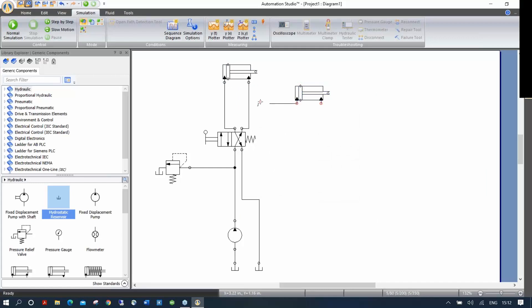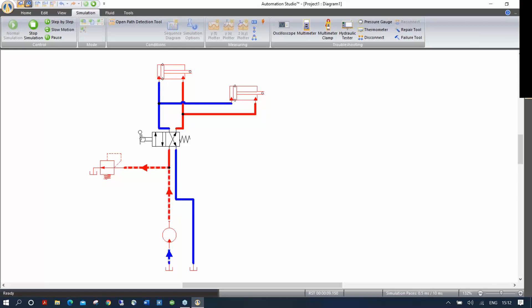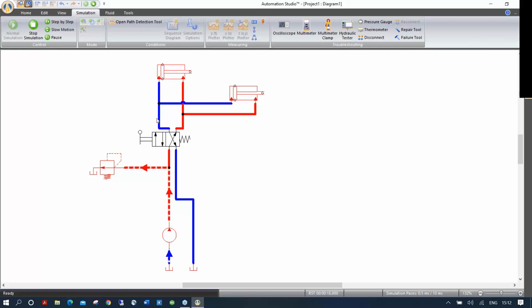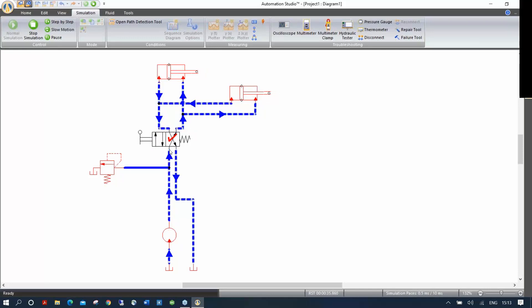Now I can connect this one in parallel with the other. If I simulate again, they both extend and retract at the same time because they have the same parameters. Something to keep in mind: I'm clicking on the lever of the directional valve, but the spring pushes it back each time. To lock a valve in a specific position, click on the spool directly and you'll see a big check mark — this means the valve is manually overridden in that position. Click the other spool to return, or click the spring or command to remove the forcing.